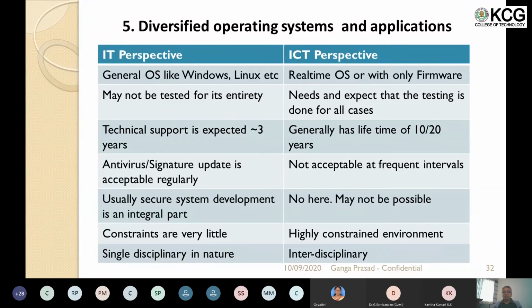Operating systems: there is a huge difference. Generally any OS is okay from an IT perspective, whereas ICS generally operates in a real-time operating system or sometimes even only firmware, because it has to work in a constrained environment where time and reliability are essential components. Such constraints are not at all important in an IT system, you have enough memory and it operates in a controlled temperature. Whereas in the ICS system it is not so, it's actually a very highly constrained environment, so even introducing security aspects becomes very difficult, since the memory and resources may not be available to add additional features to take care of security.